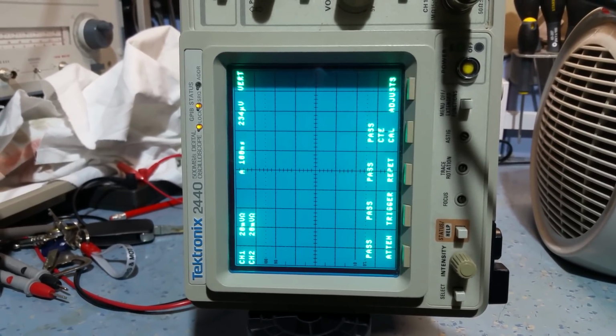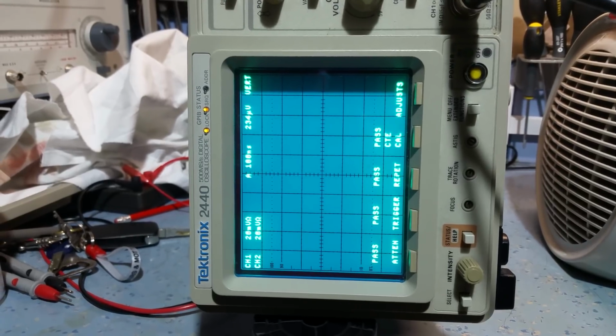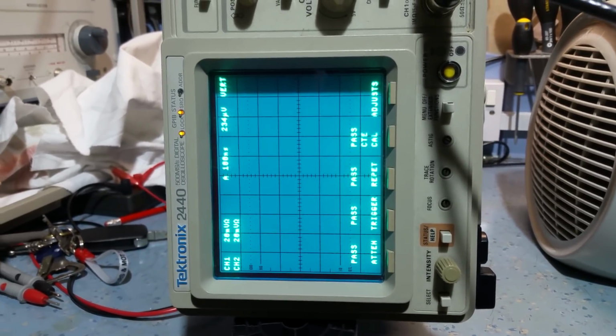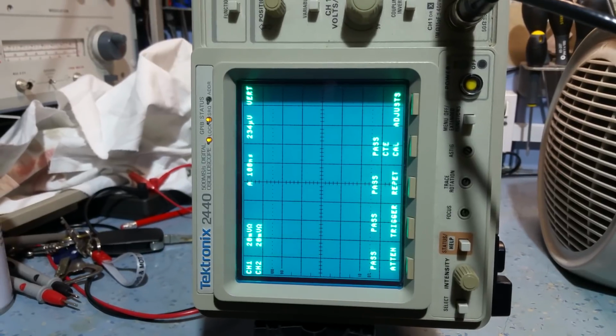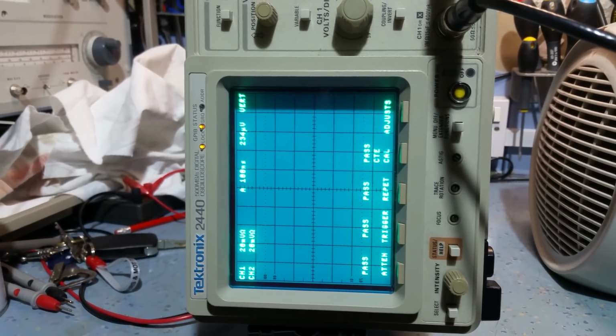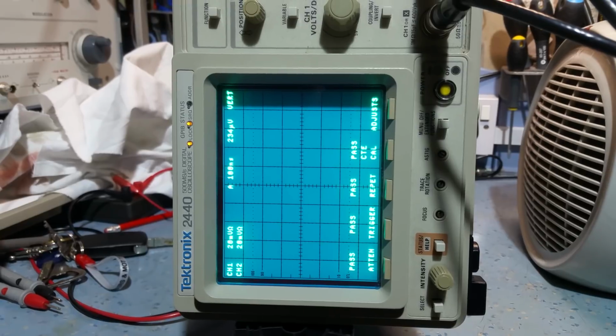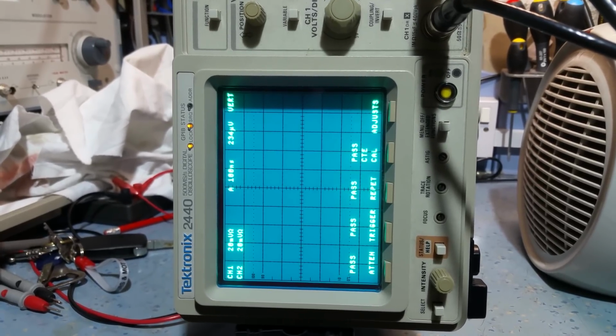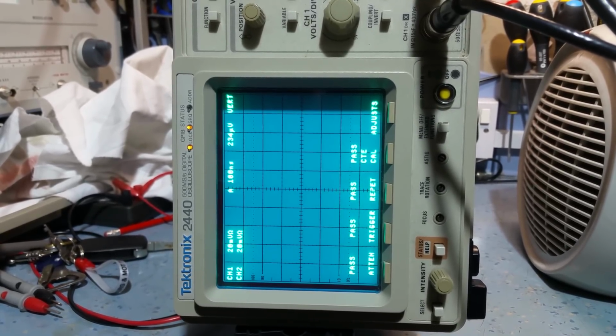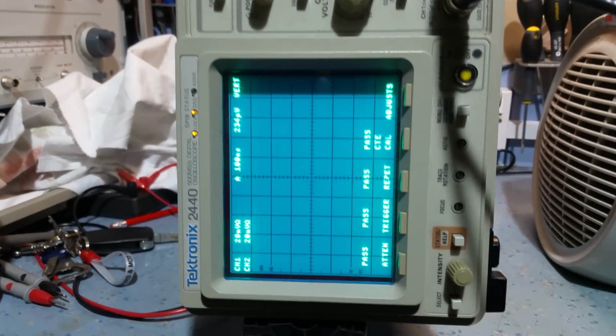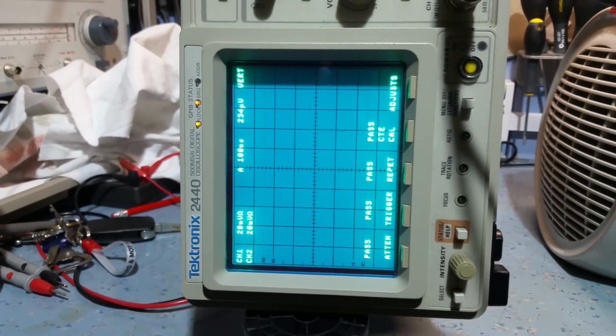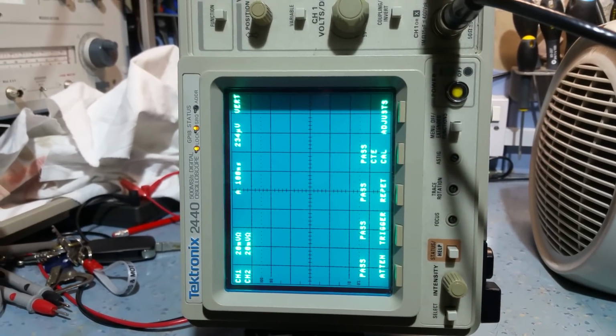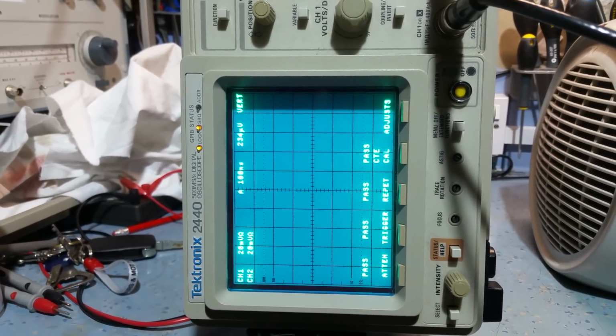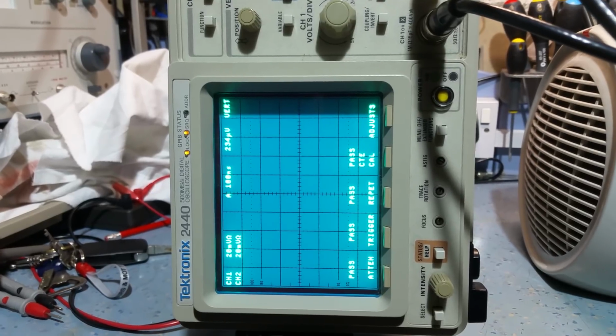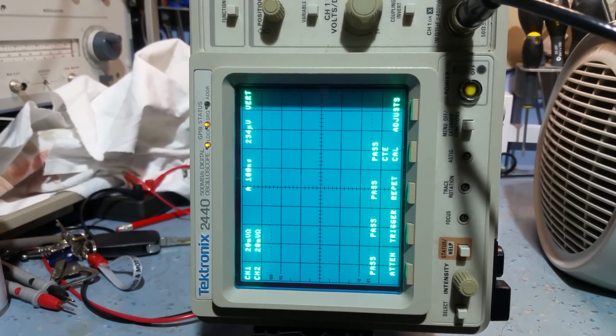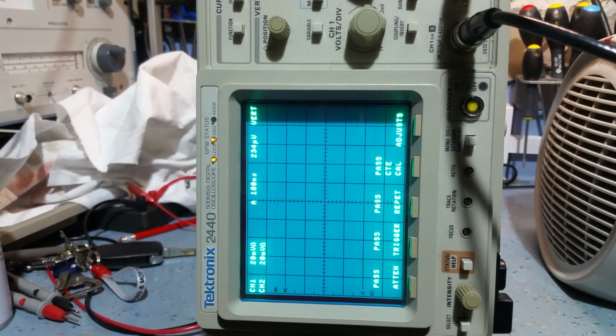Now the reason why it was failing the calibration and the process wouldn't complete was basically because it kept coming up with this problem with the CCDs. It was a really weird fault because it's not similar to a normal CCD failure you get. You don't get the strange distorted waveform, but above about 500 nanoseconds, the sweep would just stop. You couldn't sweep, and that's a clear sign that there's something wrong with the CCD side of it, because that's when the CCDs take over.